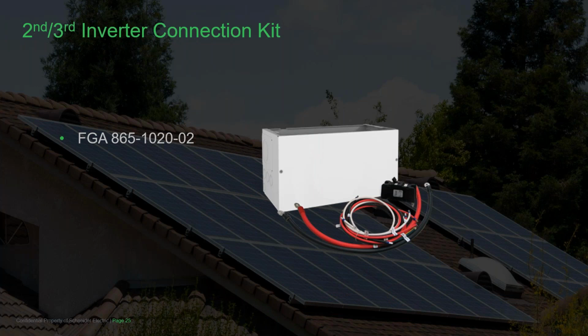A connection kit will be needed for each additional XW Pro. So the PDP gives you the balance of system for the first one, and then for phase B and C, you'll need an additional connection kit for each one. That's part number 865-1020-02. This includes a 250 amp DC breaker, conduit box, DC cables, and AC wires.